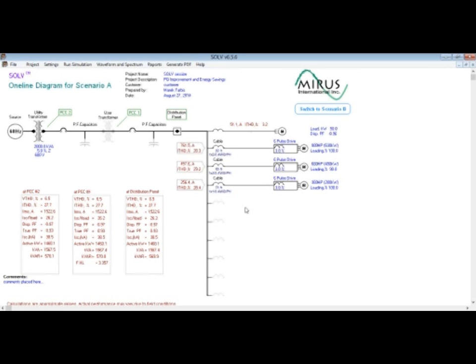So we don't need a contactor for this reason, because the reactive power seen on the input side of the filter is very small. If a standard generator is used, it can accept up to 20% capacitive reactive power. We'll have no problem with our filter.